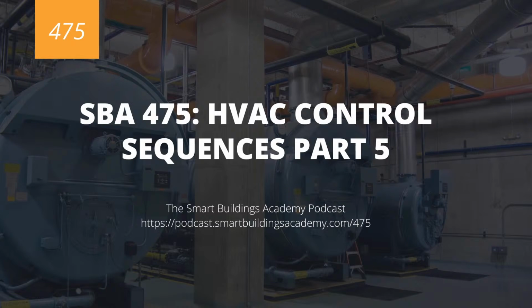So let's take a look at a sequence. In this case, the hot water system is enabled for operation when the outside air temp is below 6 degrees. Looks pretty similar, right? Now here's a little nuance. Each boiler has a circulating pump associated with it. This circulating pump circulates water inside the boiler, and then it's the primary pump that will then draw water from that circulating loop out to the primary loop. So right here, these boilers are going to be focused on maintaining a temperature, either a reset temperature as we talked through or a constant temperature.